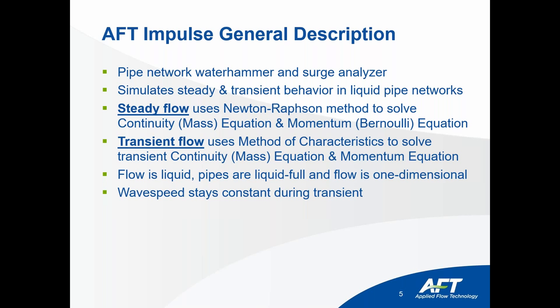The constant wave speed assumption is important regarding cavitation — if you have cavitation, in reality your wave speed is going to change. Impulse is very good at modeling discrete levels of cavitation as long as it does not become a dominant characteristic of your system. This is a limitation of the mathematical models, not of Impulse itself, because cavitation is a very heavy two-phase flow phenomenon.